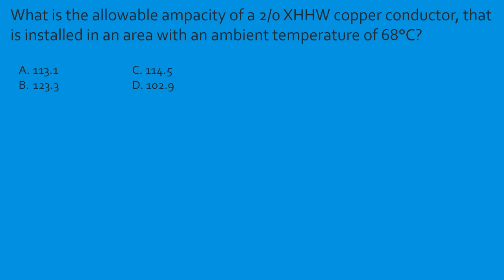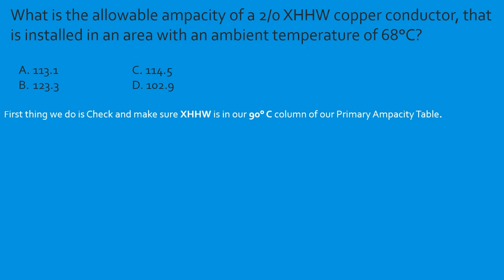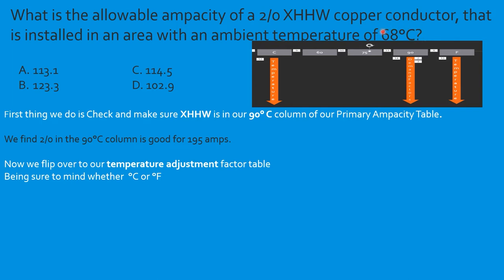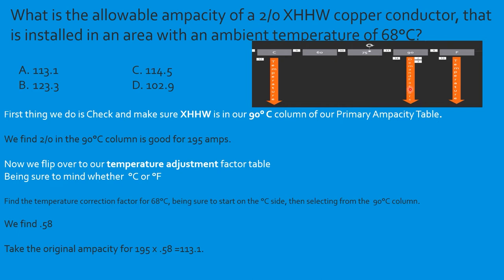Question: What is the allowable ampacity of a 2/0 XHHW copper conductor installed in an area with an ambient temperature of 68°C? XHHW is listed; 2/0 copper is 195 amps. Head to the temperature adjustment table — this question specifies Celsius, so start on the left-hand side, come down to 68°C, then shoot all the way over to the 90°C column. Correction factor is 0.58. So: 195 × 0.58 = 113.1 amps. Select A. A wire once good for 195 amps is now only safely rated at 113.1 amps.